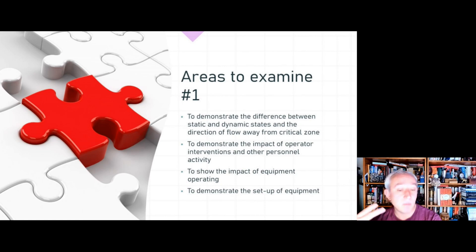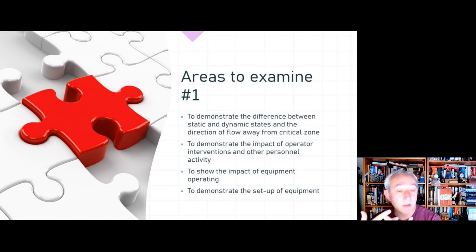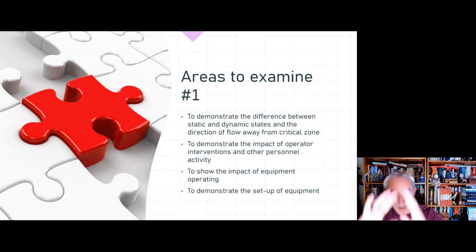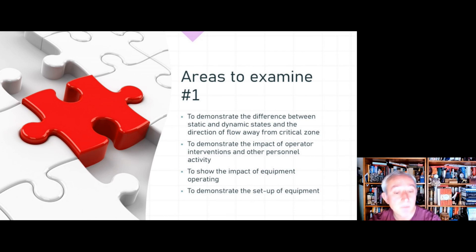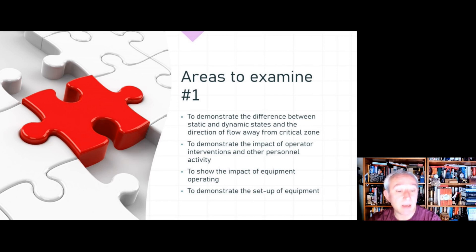Some examples of what to examine: we want to demonstrate the difference between an at-rest state and an in-use state, and the direction of unidirectional flow in relation to the critical zone. Ideally we want to see it carrying particles away from the objects we're most concerned about. We also want to demonstrate the impact of operator interventions and other personnel activity, and to show the impact of how equipment operates.